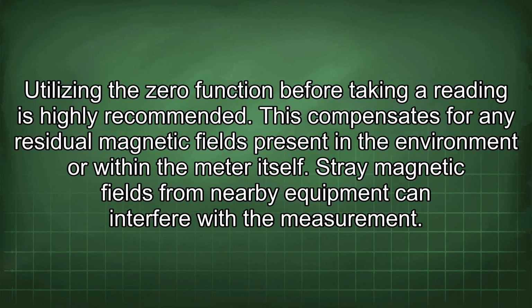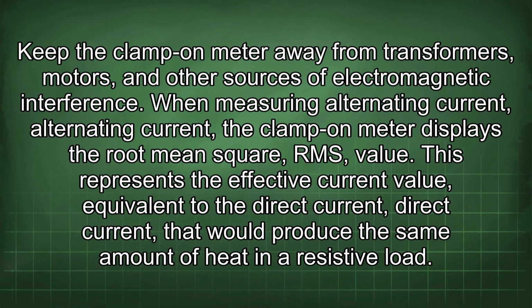Utilizing the zero function before taking a reading is highly recommended. This compensates for any residual magnetic fields present in the environment or within the meter itself. Stray magnetic fields from nearby equipment can interfere with the measurement. Keep the clamp-on meter away from transformers, motors, and other sources of electromagnetic interference.